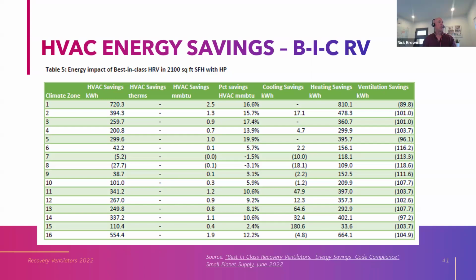Alan asked about best-in-class recovery ventilators, and we're trying to be brand non-specific, of course, with that term. But it's loosely based on the Zehnder units, that are quite a bit more money, but have recovery effectiveness in the 90% range and watts per CFM in the 0.5, 0.6 range. That's all laid out in the study.